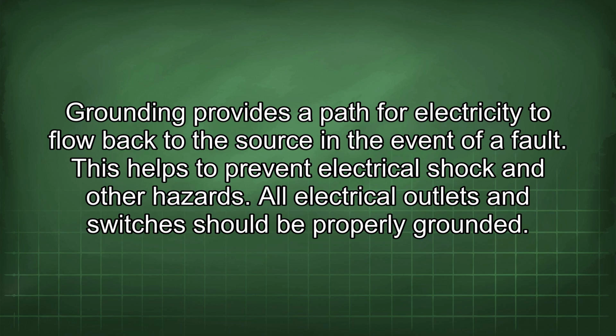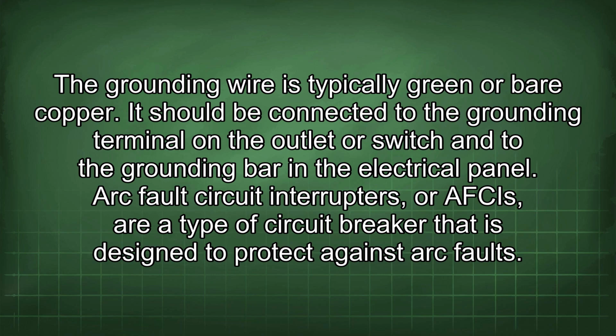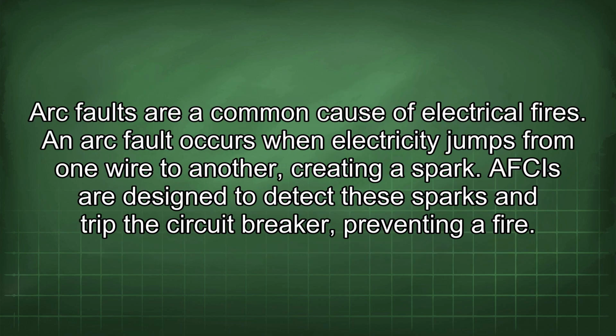All electrical outlets and switches should be properly grounded. The grounding wire is typically green or bare copper. It should be connected to the grounding terminal on the outlet or switch and to the grounding bar in the electrical panel. Arc fault circuit interrupters, or AFCIs, are a type of circuit breaker that is designed to protect against arc faults.